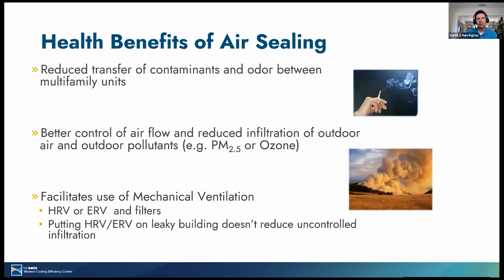Heat recovery ventilators and energy recovery ventilators are the gold standard currently for ventilation systems. They have a supply and a return fan. They exchange heat with one another, so you're reducing the ventilation-related load with those systems, but they're balanced. So putting an ERV or an HRV on a building doesn't reduce uncontrolled infiltration, and it might even make it worse relative to a building that's using exhaust-only ventilation. Because once you balance the pressure with outside, you're at the whim of the natural wind and stack effect causing infiltration. So if you're going to install those devices, you really need a tight envelope for them to work properly.